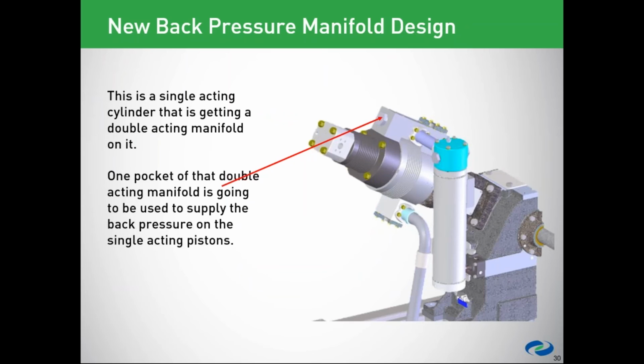So, the new back pressure manifold design. Instead of having tubing that went from between the two cylinders, we used to have tubing that came out the sides of these and then would get fed in the front side of the scrubber bottle. Now the manifold itself, what they've done is take a double acting and put it on the single acting cylinder, and they're these two single acting cylinders, and they're taking that required gas for the difference in size of these two cylinders, and they're actually putting it in front of to be used, or if the larger cylinder needs more gas, then we take it out of the scrubber. I'm not sure if that's confusing or not. This might be a good question.